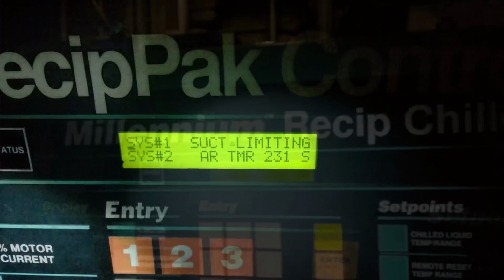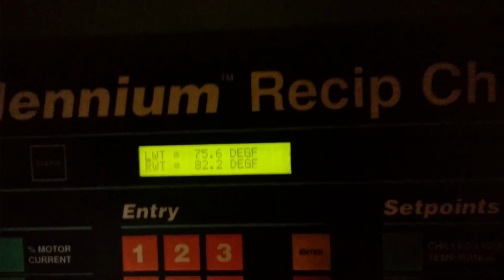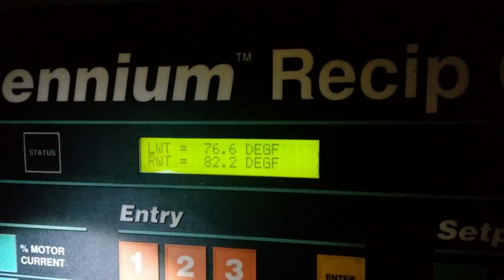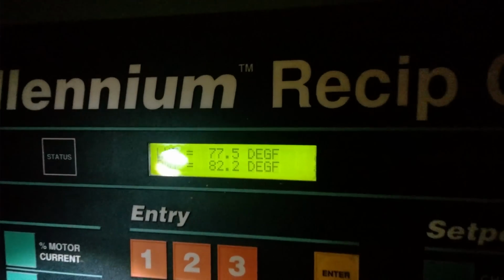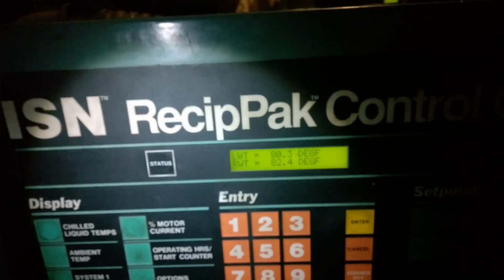Just turned on the primary pumps to the chiller. Ooh, chiller 1 just started too. Sweet. Hopefully that'll kick on here in a second. That's reading pretty normal now. 82 return water and 76 leaving water, and yep, system loop's pretty warm. Got about a 2-degree drop so far.